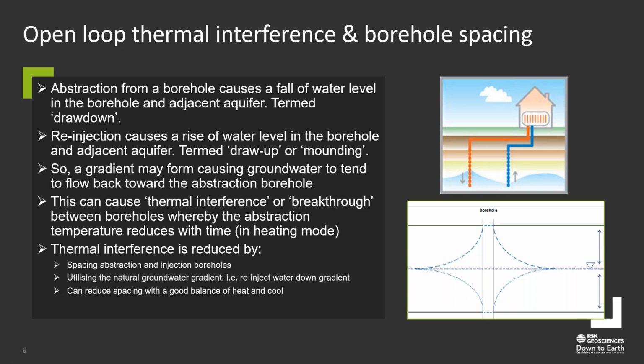You can also take advantage of the natural groundwater gradient. For example, if you're trying to heat this building, you're taking water from one direction, and if the groundwater flow is towards the left, re-injecting the cooler water means it moves away, so there's less chance of thermal interference and a backup of cold water towards the warm abstraction point.